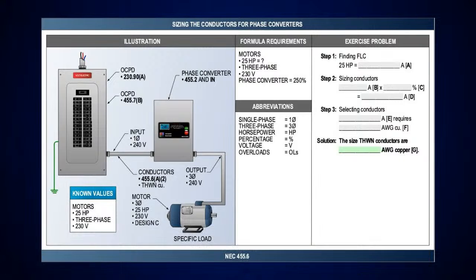So it's a 230 volt motor, and to me personally, what I'm gonna say on this, Raymond, is the way I look at that is that's a nominal voltage. So as long as you have a nominal anywhere from 230 to 208, the only time I've had issues with that is when you have a large demand, because what happens is that 208 volts drops to like 196, that 208 volts drops below that manufacturer recommended voltage, and then that'll kill the motor. So you have to watch that.